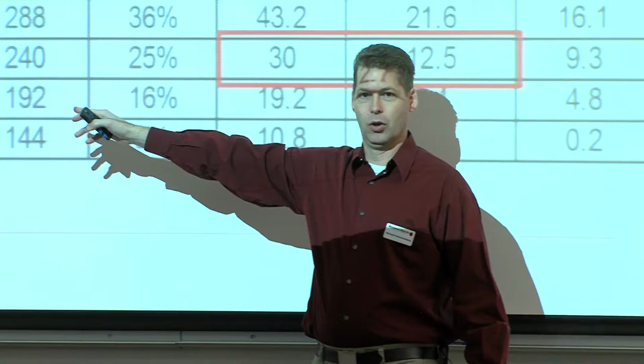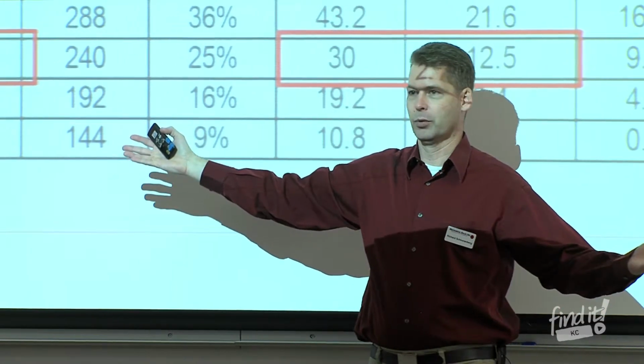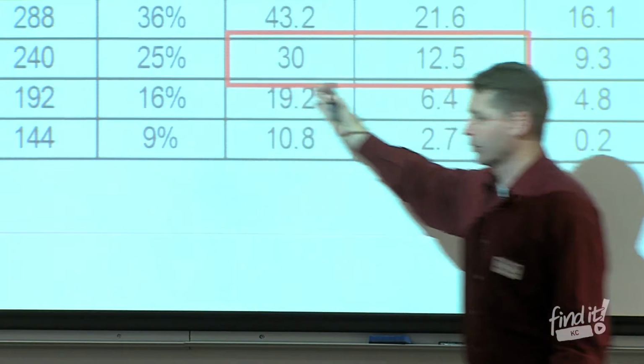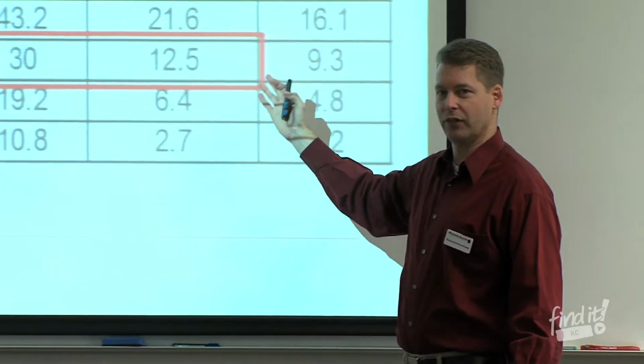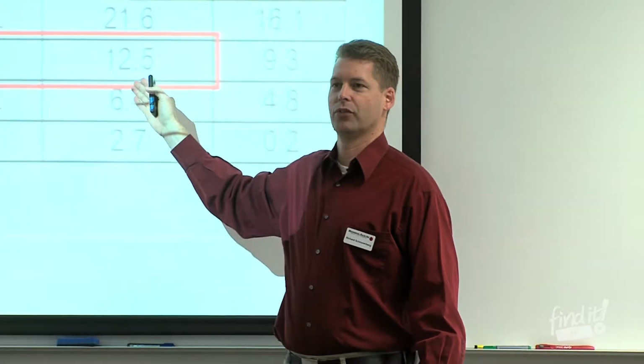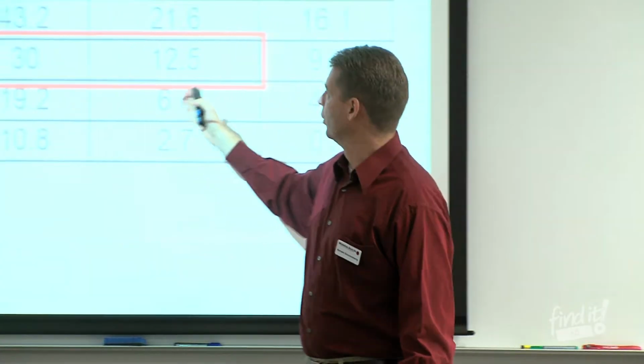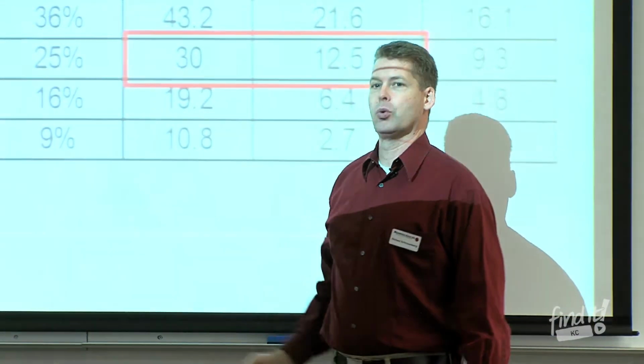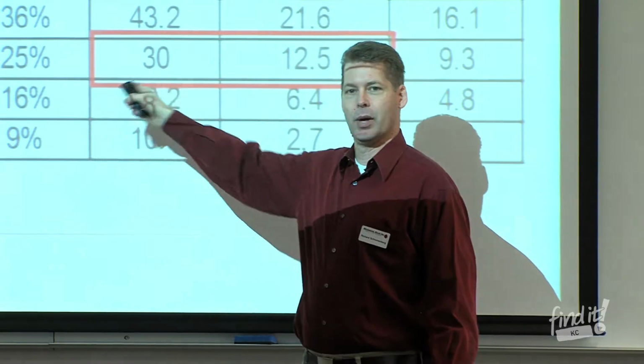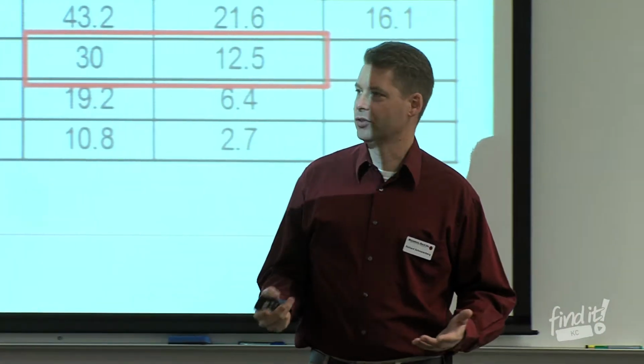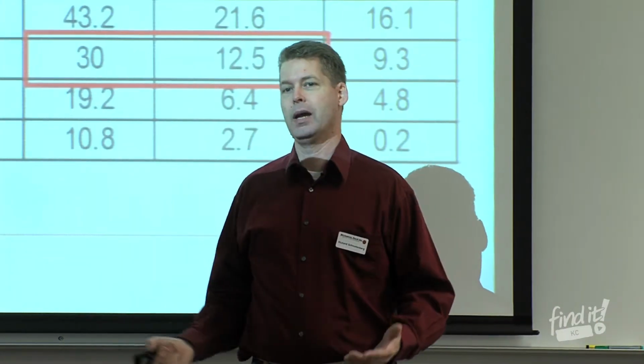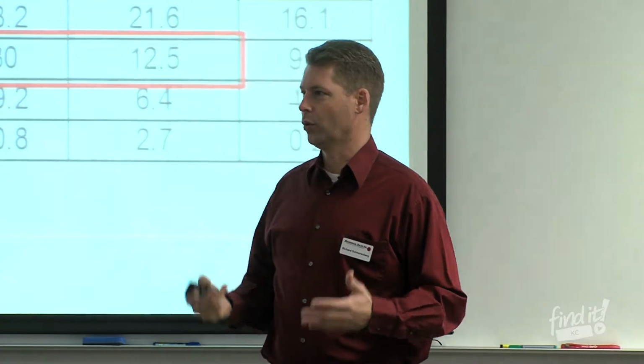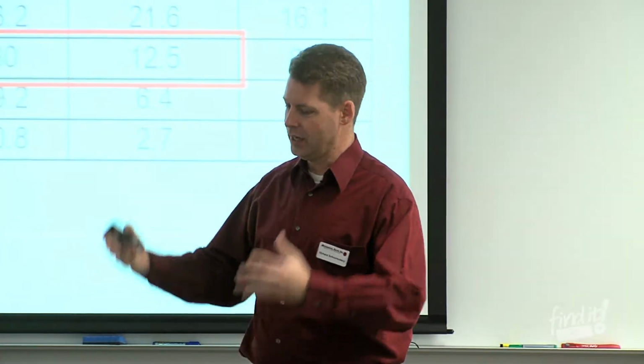And at 50% flow, people think, well, if I'm slowed down to 50%, that'd be half my energy, right? No, because of the way that energy consumption works in a fan and a pump, you're actually at 12.5% of your energy at that point. So in this example we reduced a 120 amp motor down to 30 amps by going half speed. There's a huge amount of energy savings you can get on these things, so therefore a huge payback by being able to take an existing motor or a new design system that you've got a VFD and deciding to slow that motor down.